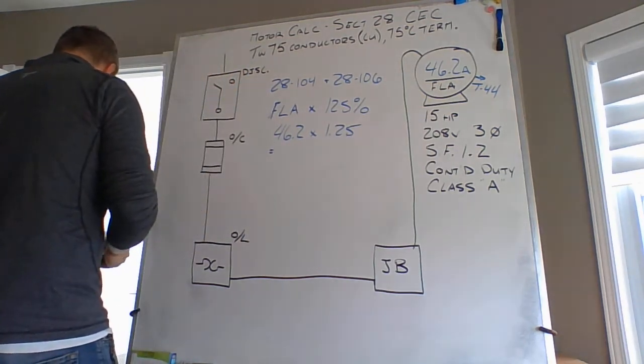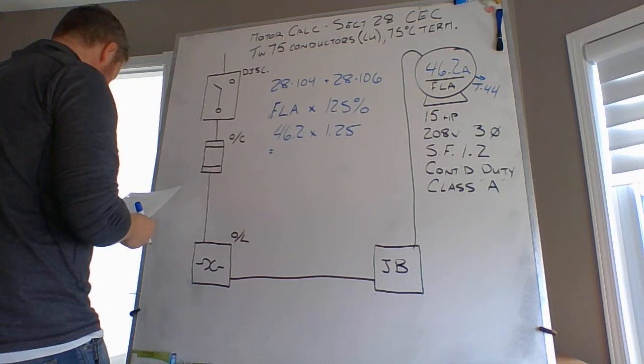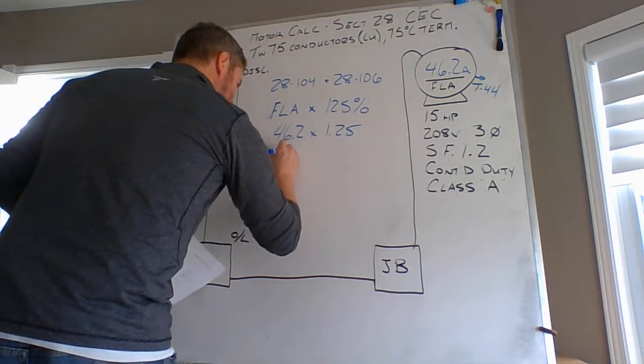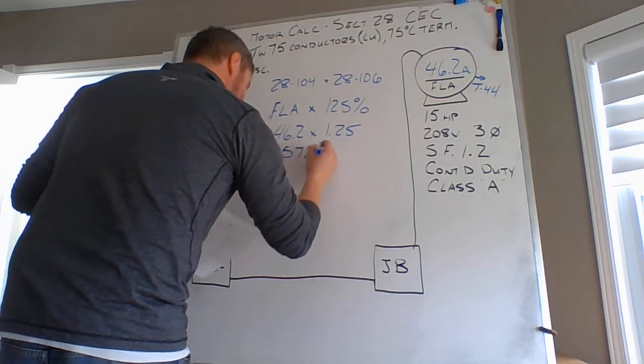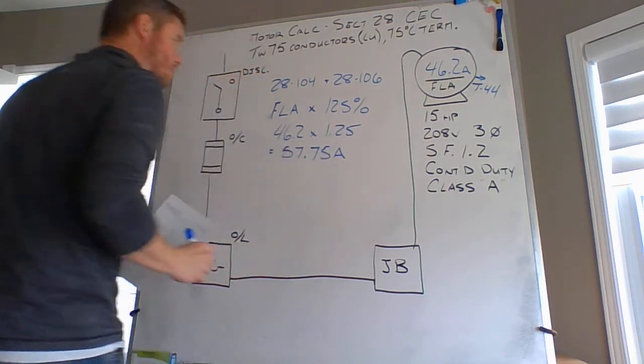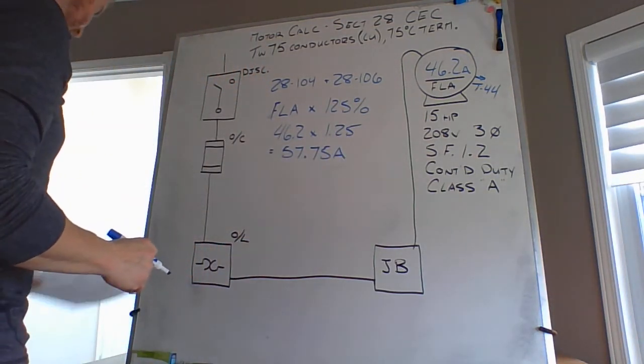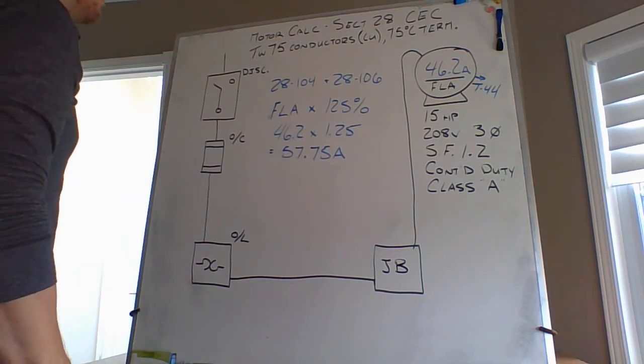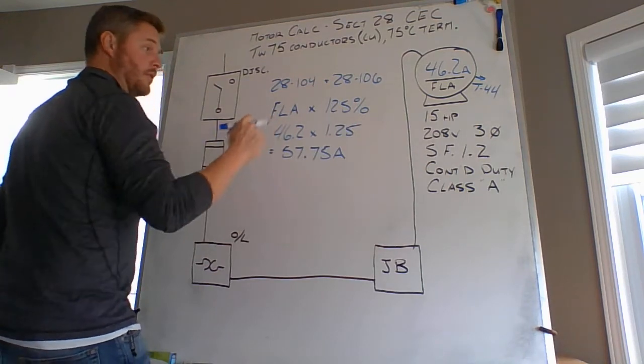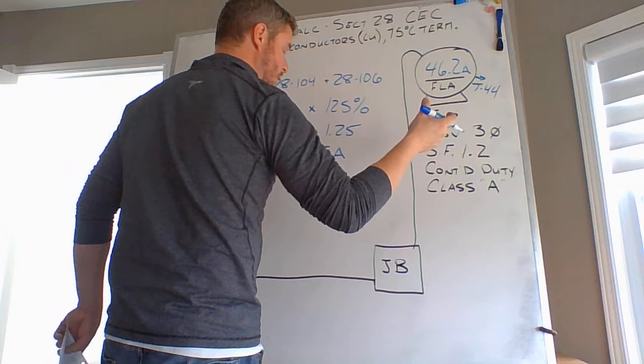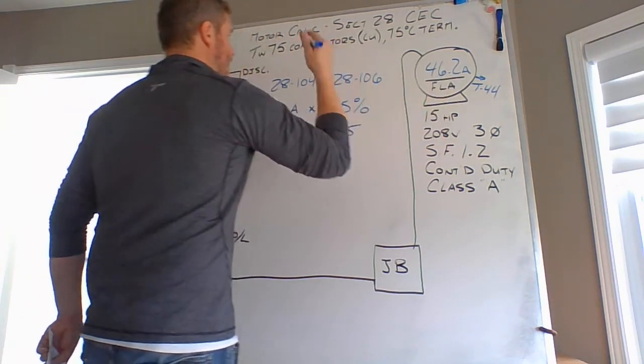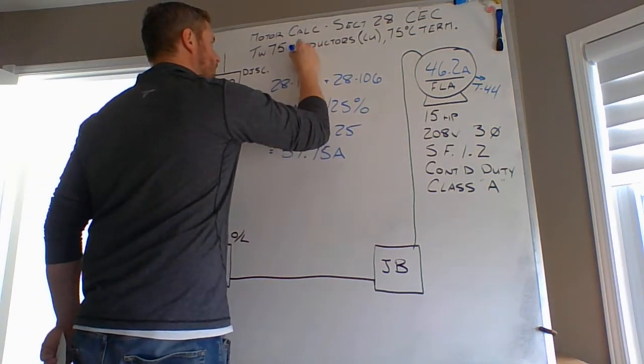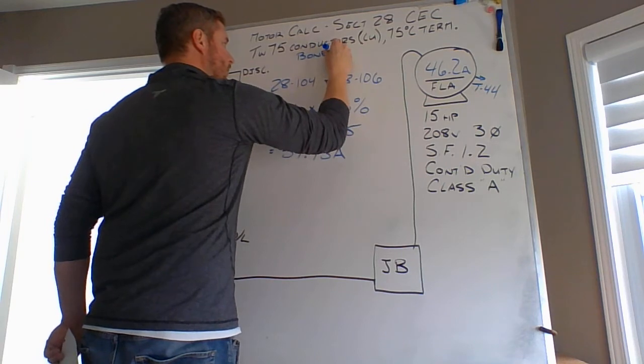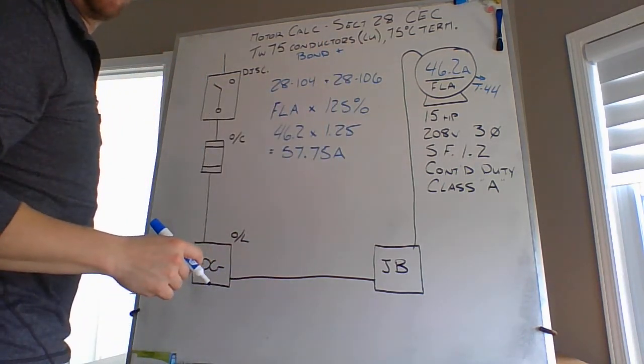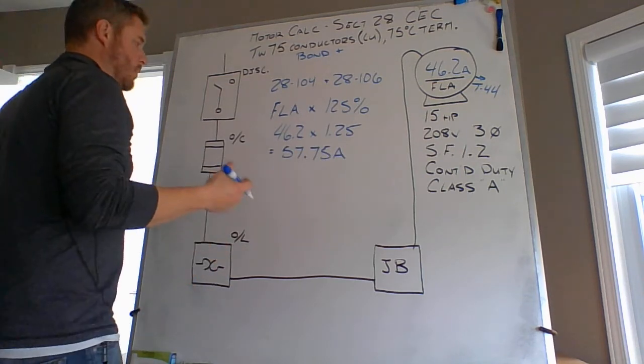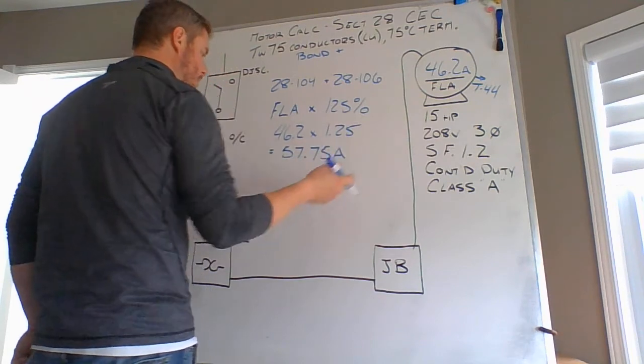If I do that calculation, I should end up somewhere in the 57.75 amp range, somewhere around there. 57.75 as my calculated minimum ampacity for my conductors. Now, this is a three-phase motor, so I have a red, a black, and a blue feeding this motor, as well as a bonding conductor. I'm going to throw a bonding conductor in there anyways, just to be safe. So at this point in time, I'm 57.75 amps as a minimum capability of my conductor.